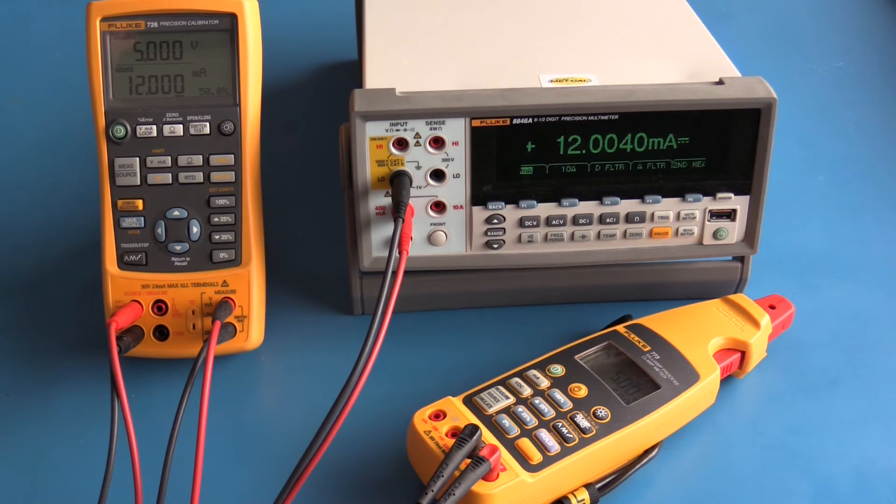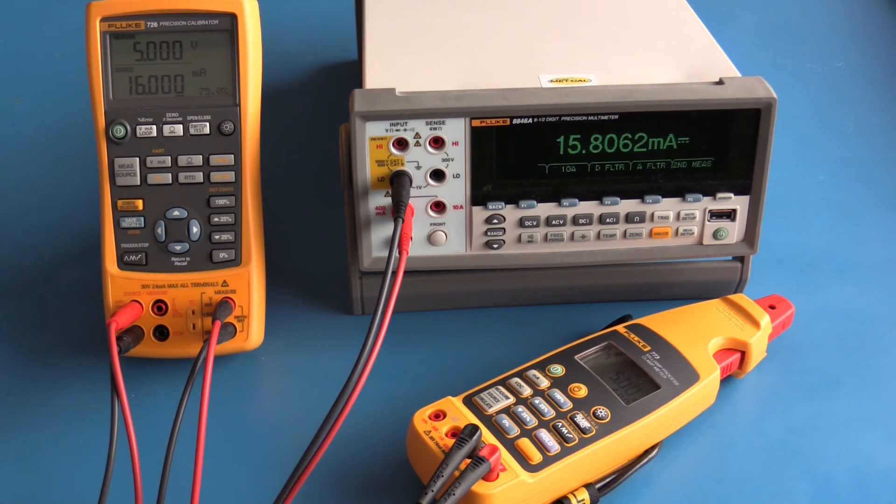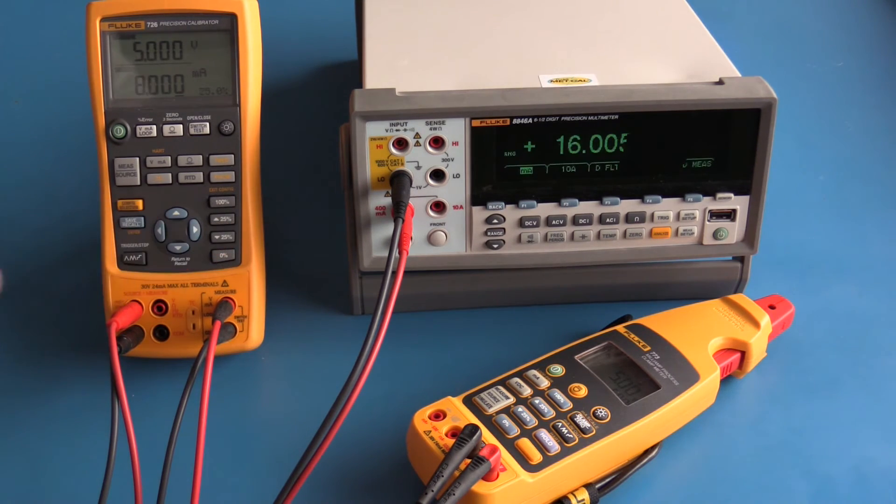The milliamp range on the Fluke 726 is 0 to 24 milliamps, currently at the 50% value which is 12 milliamps. I can go up and down in 25% increments. That's 16 milliamps, and that's 8 milliamps. It is close to what the Fluke 8846a is measuring.